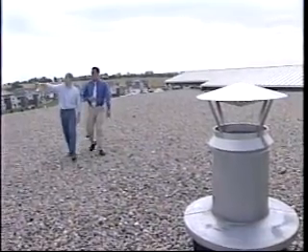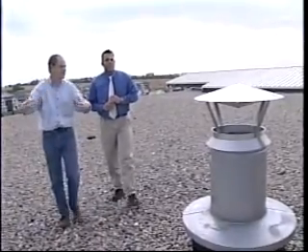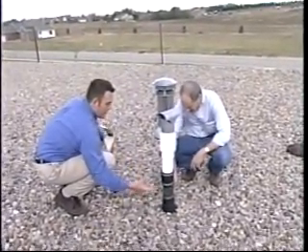We had theorized that possibly sewer gas was getting into the building because it was getting drawn in through the fresh air intake on the HVAC unit on the roof. And we did in fact find that there's a flexible pipe that was on top of the stack. It had been blown off by the wind.